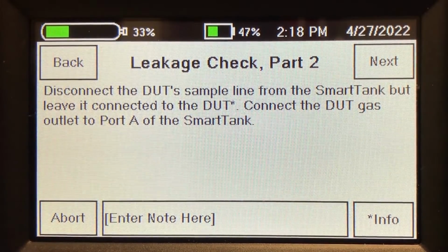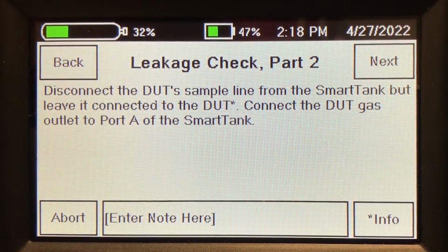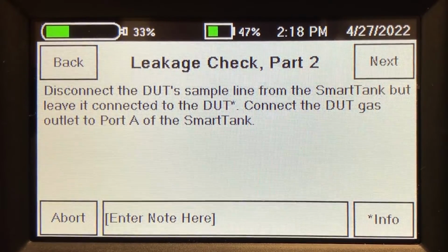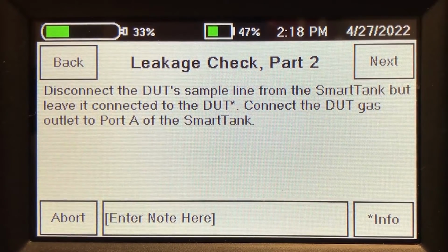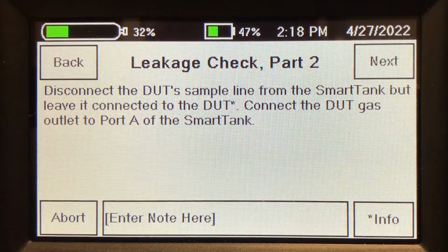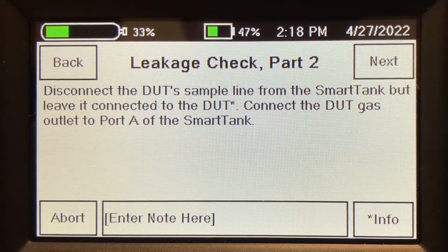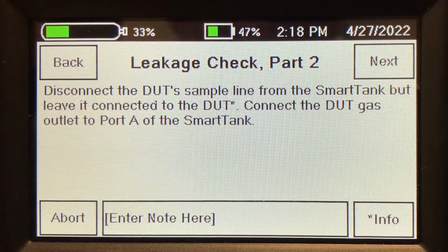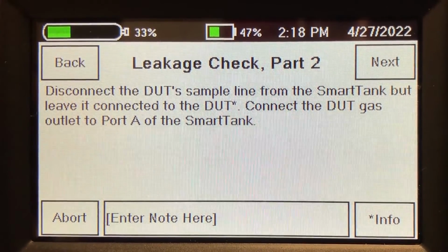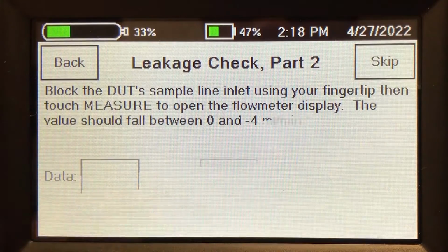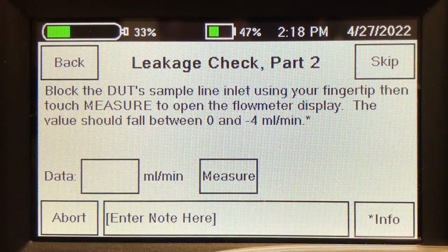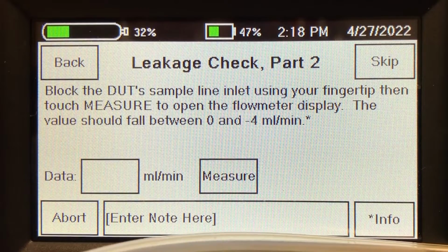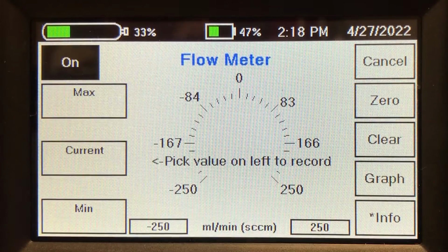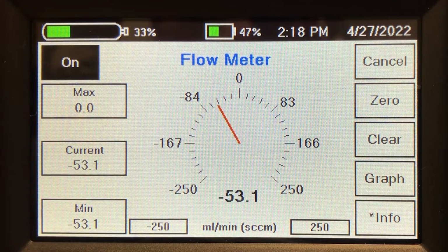Gotta grab an adapter here, because I'm going to connect the exhaust line of the extension module to port A on the smart tank. So port A on the smart tank is the port that does flow measurements and pressure measurements. Okay, get that guy connected. Now it's going to have me plug the sample line of the extension module and measure what the flow changes to. So right now the flow coming out of the exhaust port is approximately 53 milliliters a minute.